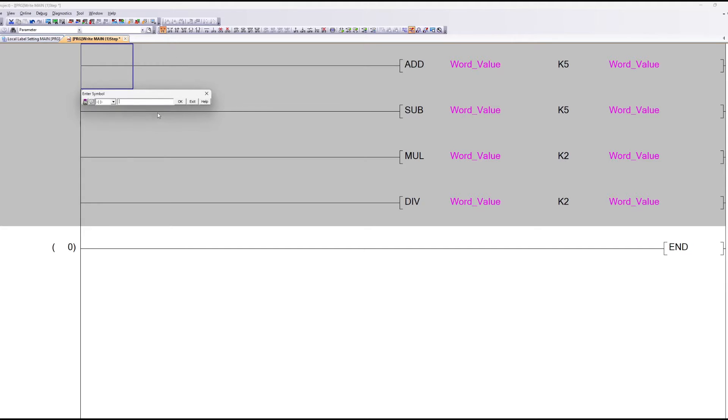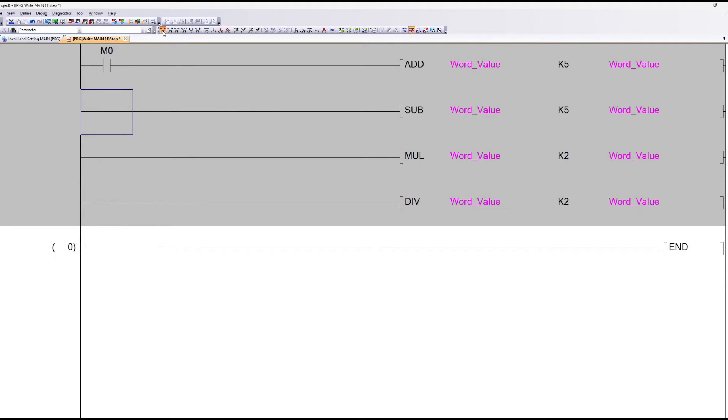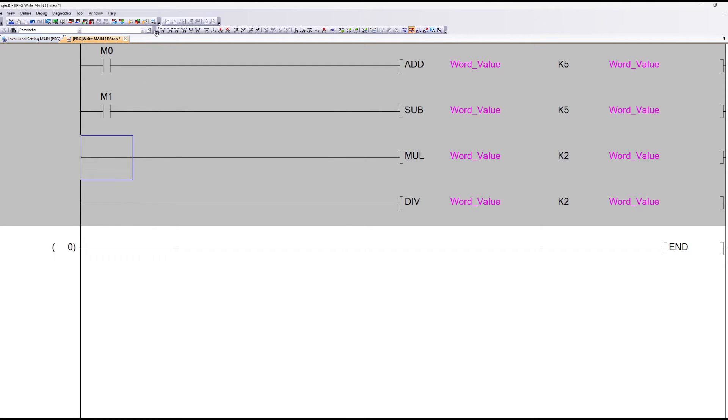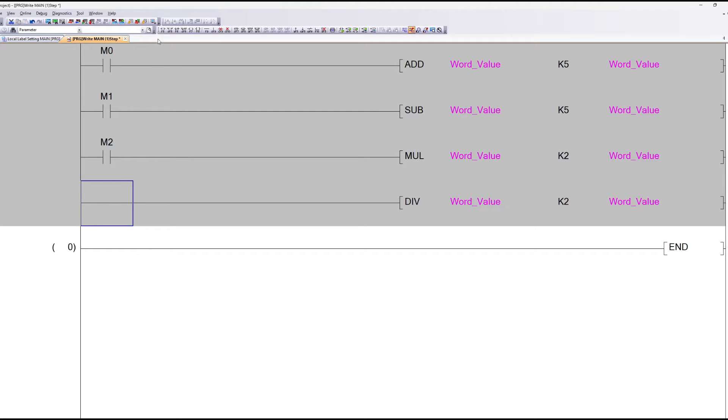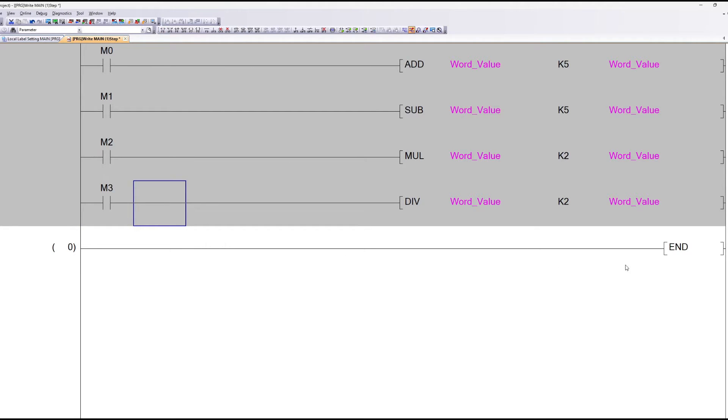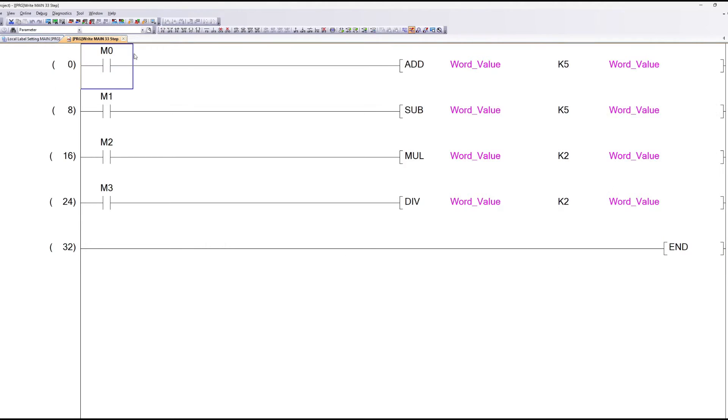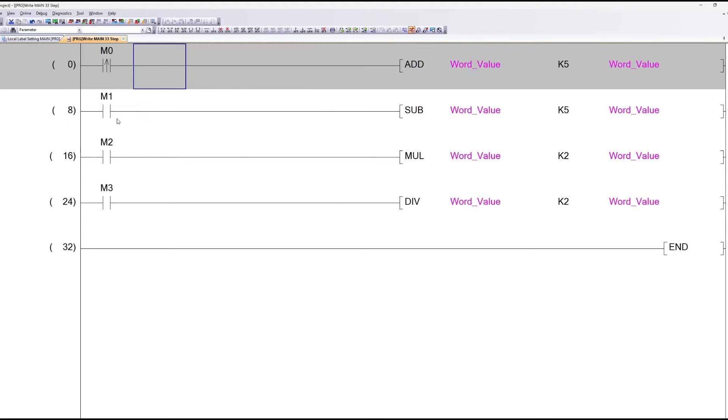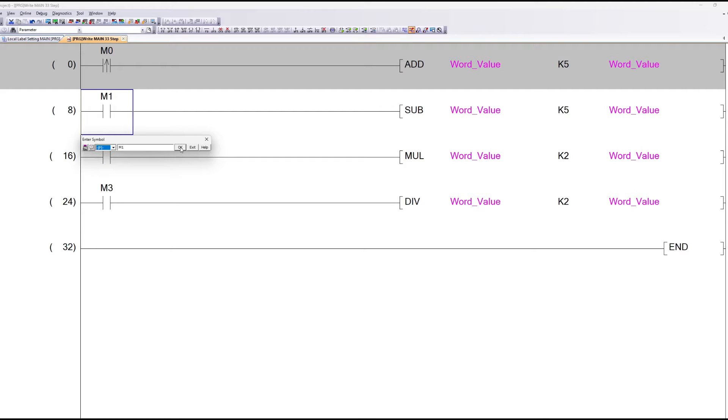I will add a memory bit for each math operation, so I can trigger it to make the math functions. The memory bits will need to be a positive one-shot pulse. Else it will continue doing the math function for each of the PLC scan cycle.